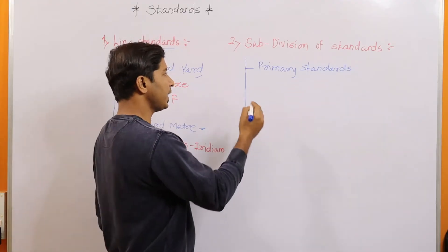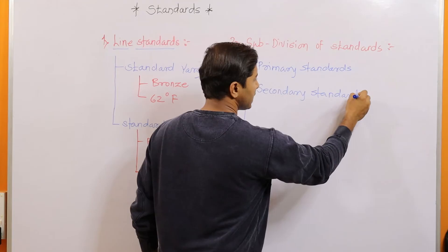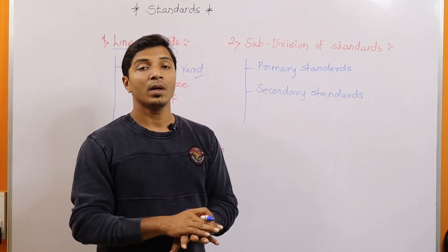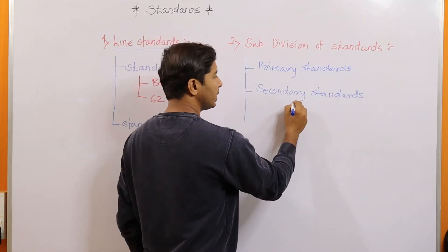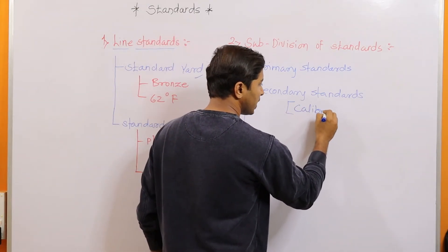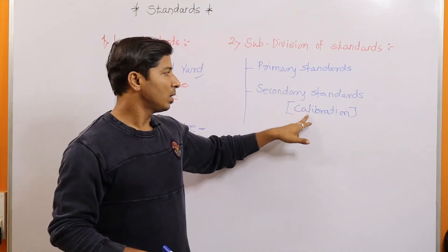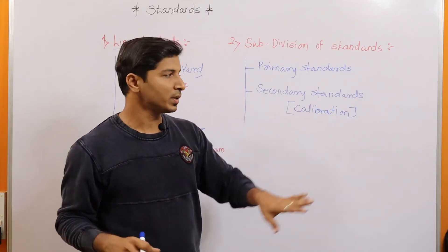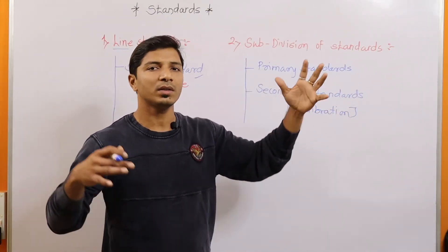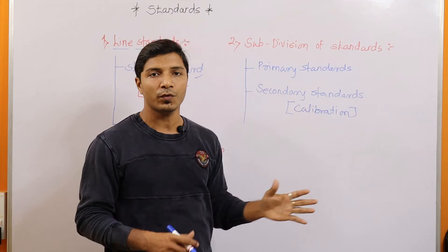The second category is secondary standards. These standards are also preserved in careful conditions and are not for ordinary or frequent use. These can also be called calibration standards, because they are used for calibration purposes — to check the accuracy of instruments. These standards are not widely used in industries. They are preserved in standard labs, and whenever instruments require calibration, these secondary standards are used.